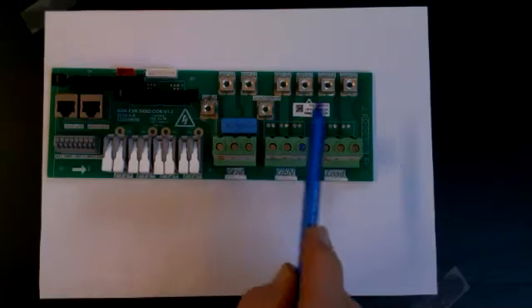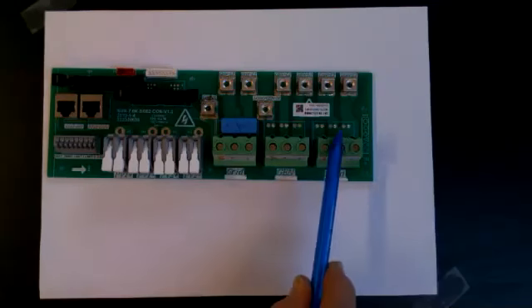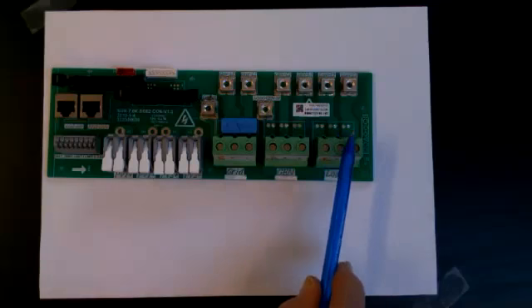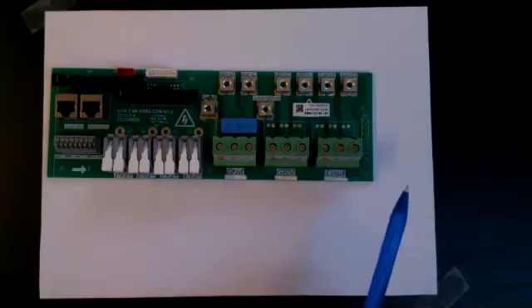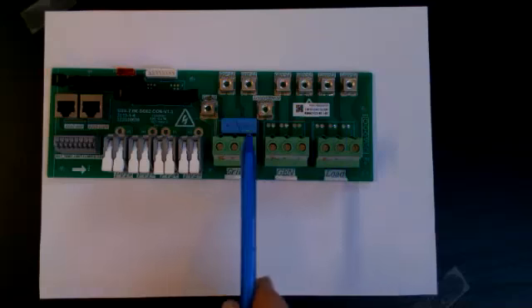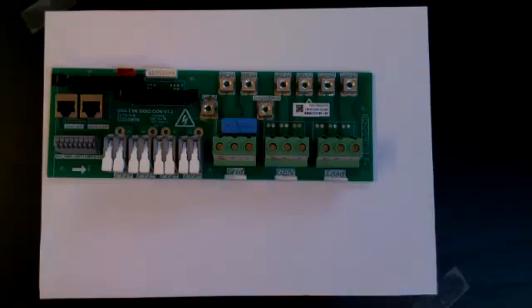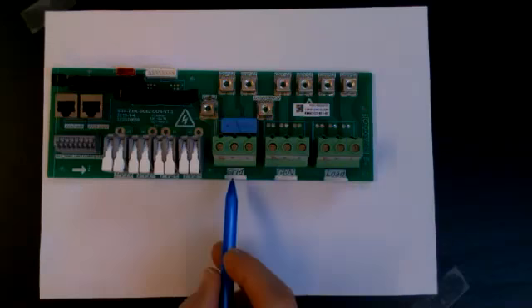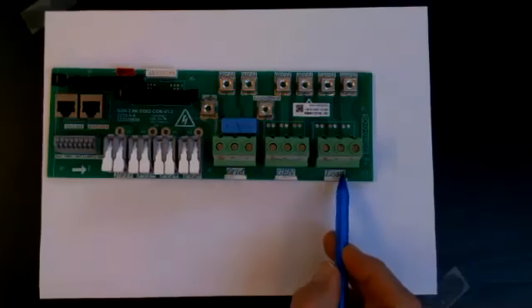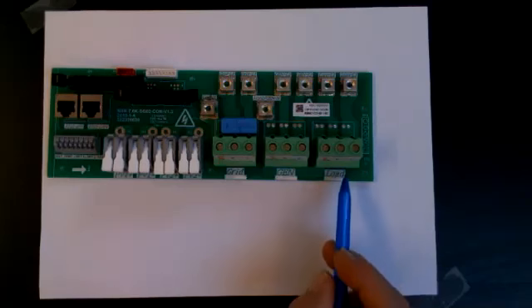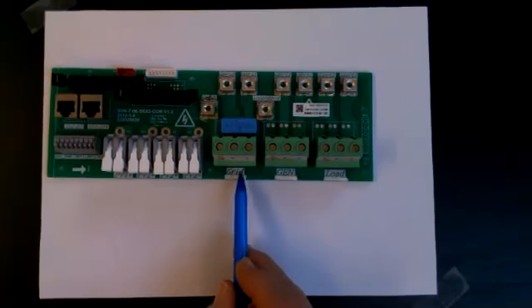Some people think, oh, that's in and that's out. It's not. That's a UPS. That's an uninterruptible power supply output. Maybe we should word it differently, but it's a UPS. This is your input, and also it's an output. And what we often need to always consider, and I'll come on to this, is that your connection on the grid side is your non-essential loads, and the load side is your essential loads. So if you have a power failure, power outage, load shedding, whatever, then the load side will continue to operate, but the grid side, you will lose it.